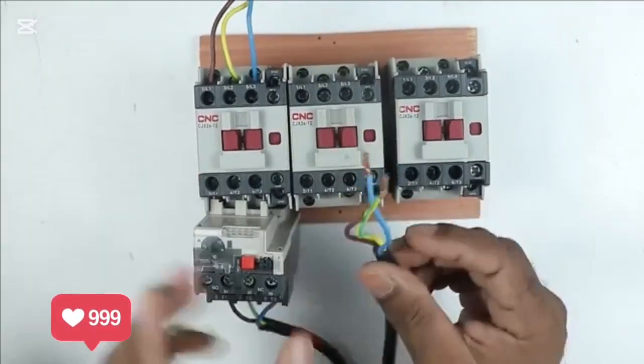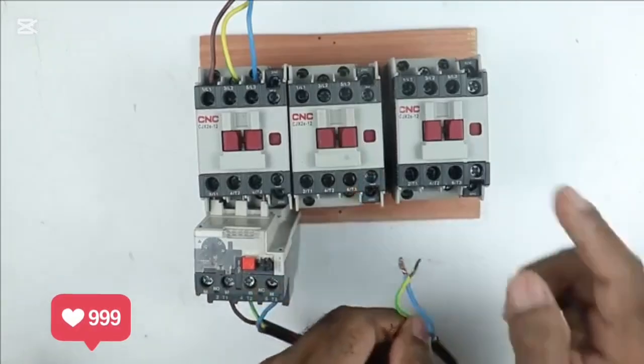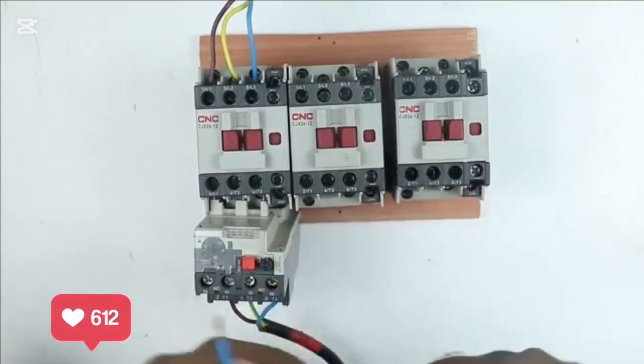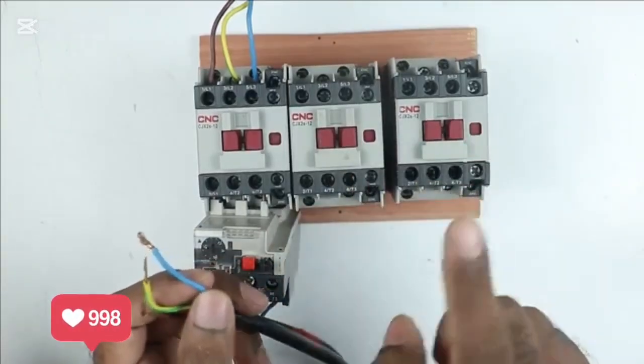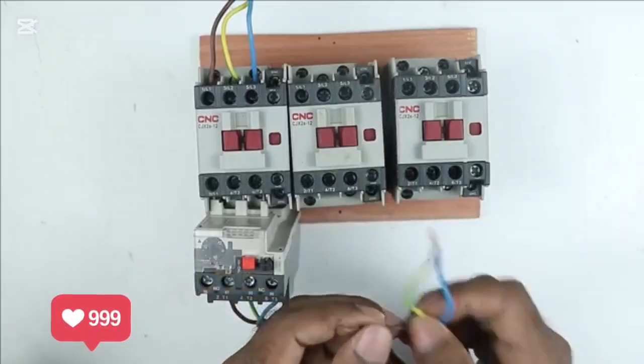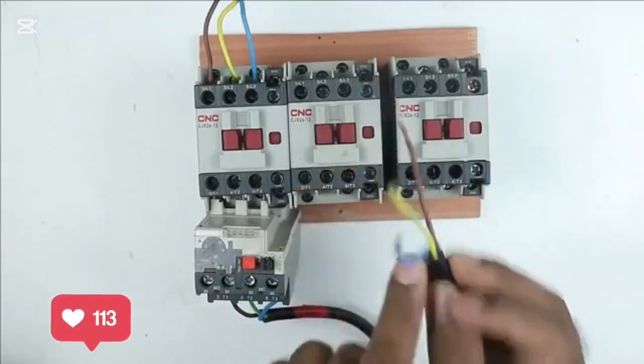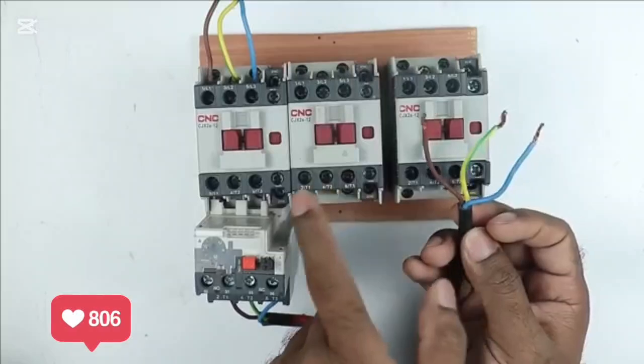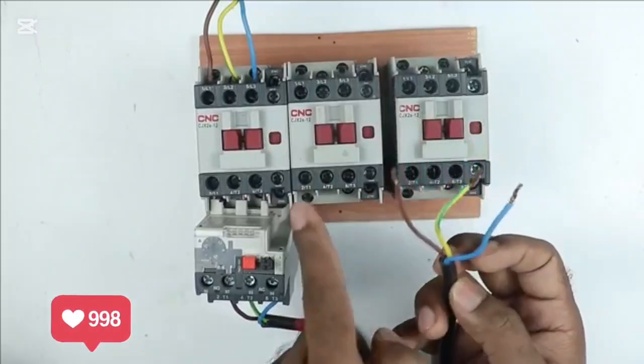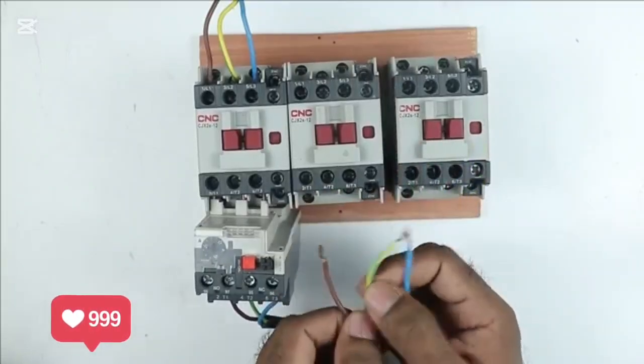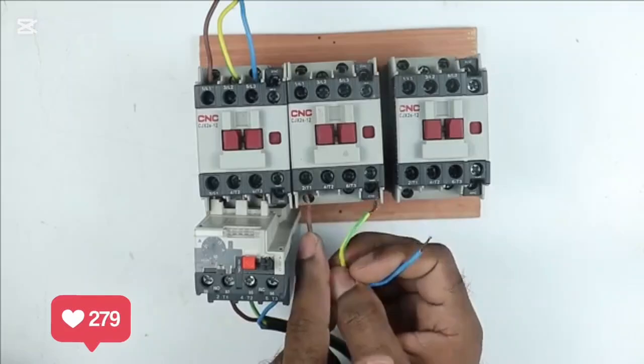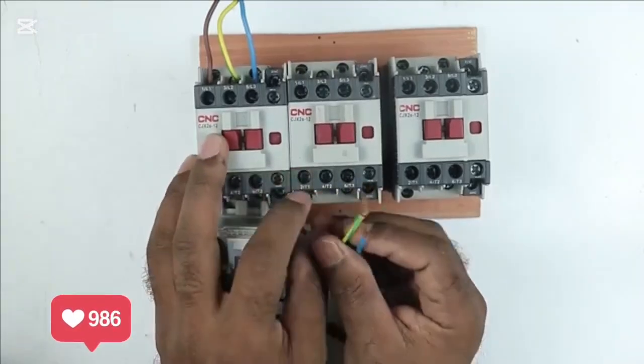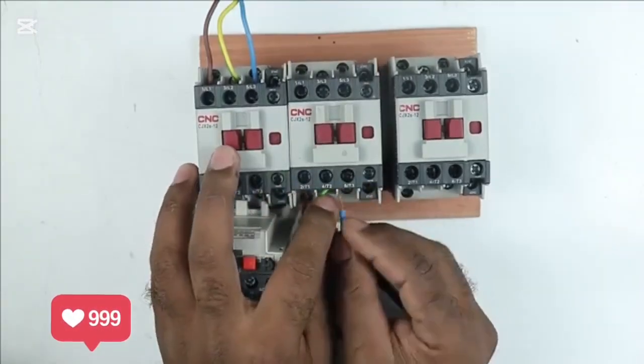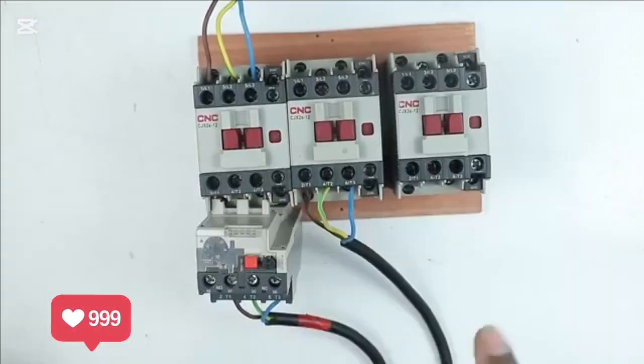So the other cable you have, take the wires of this cable and connect them to this delta contactor. I am considering this contactor as my delta contactor. Now take all the three wires of the cable and connect these wires to the delta contactor at output terminals. So with these three terminals I am connecting these three wires. With the first terminal I connected the R phase wire, at the second terminal I connected the Y wire, and at the third terminal I connected the B wire. So in RYB sequence connection is done.